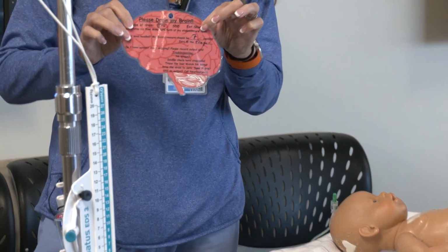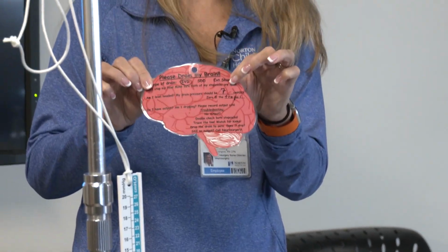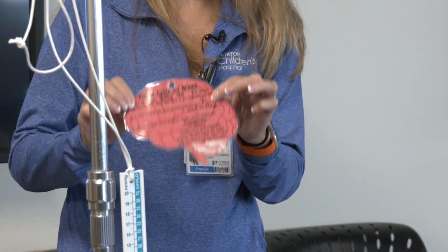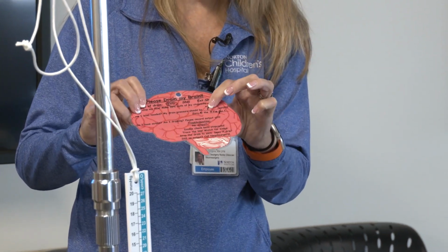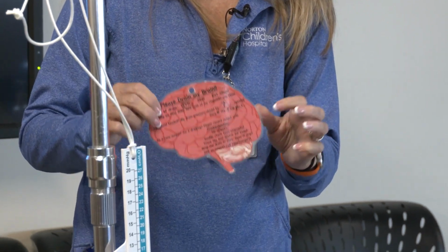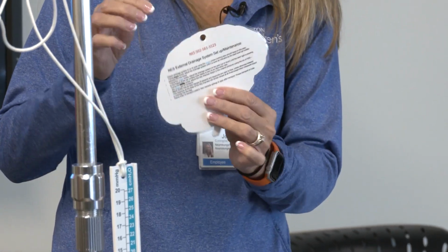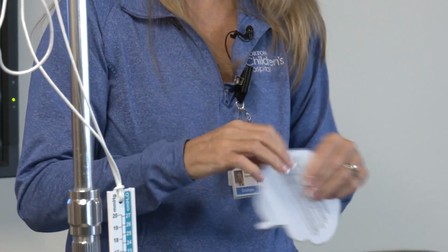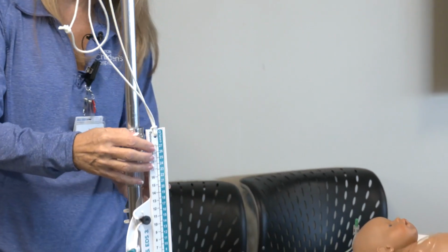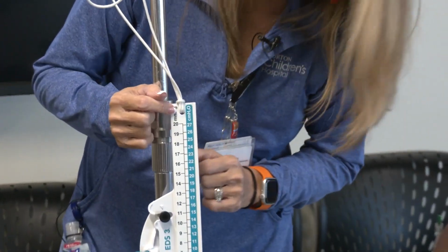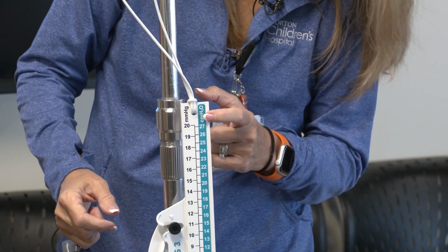Now we're going to worry about the pressure that they want. And I don't want you calling this what level is it at. It's not at a level, it's at a pressure. This number means a pressure. It's 7 centimeters of water. So it says it right here, centimeters of water. And also on the back, when it's giving you the description, it says centimeters of water. So pay attention to that, because there's two values on here. This is millimeters of mercury, and we don't use that here at Children's. And this is the centimeters of water.